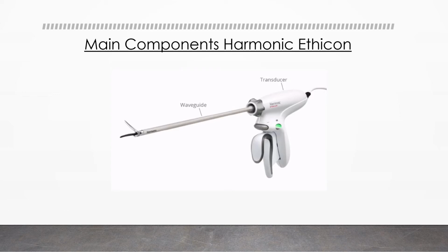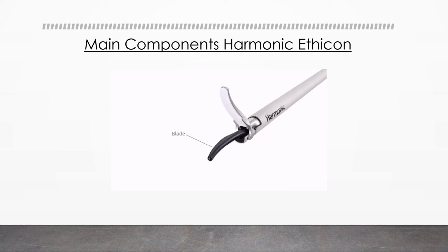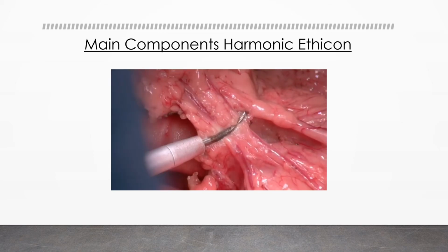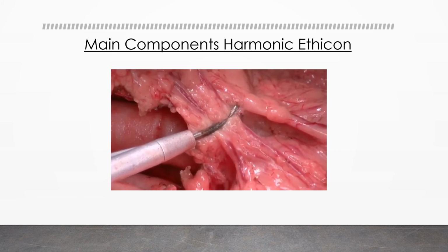The waveguide transmits and amplifies mechanical motion from the transducer to the blade. The blade is the exposed portion of the waveguide that generates the frictional heat in tissue to induce coagulation and cutting, typically with an antinode near the blade tip to maximize tissue effect. For the jaw, it compresses tissue against the blade to produce frictional heat, inducing coagulation and cutting as the tissue is pressed between the blade and the jaw.